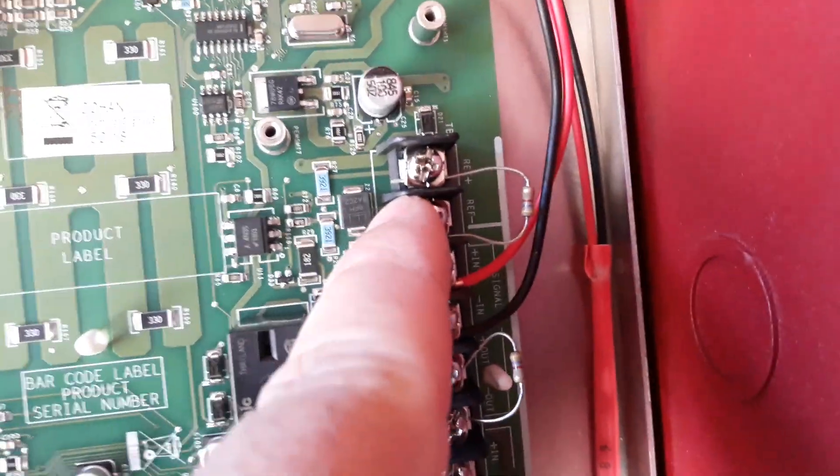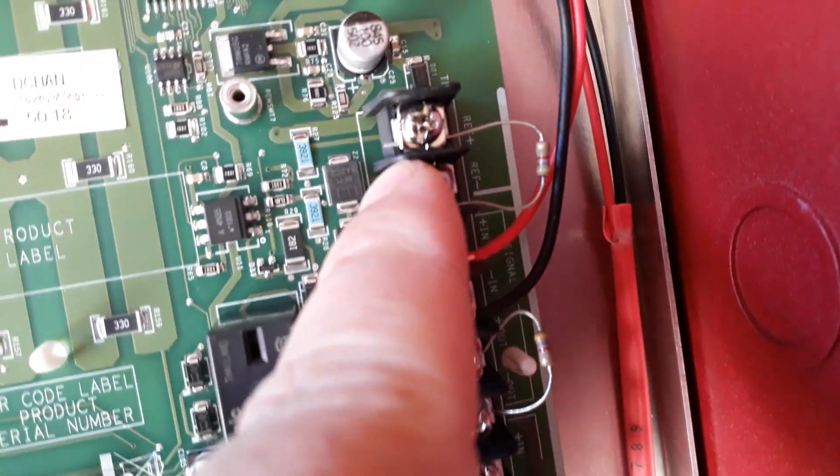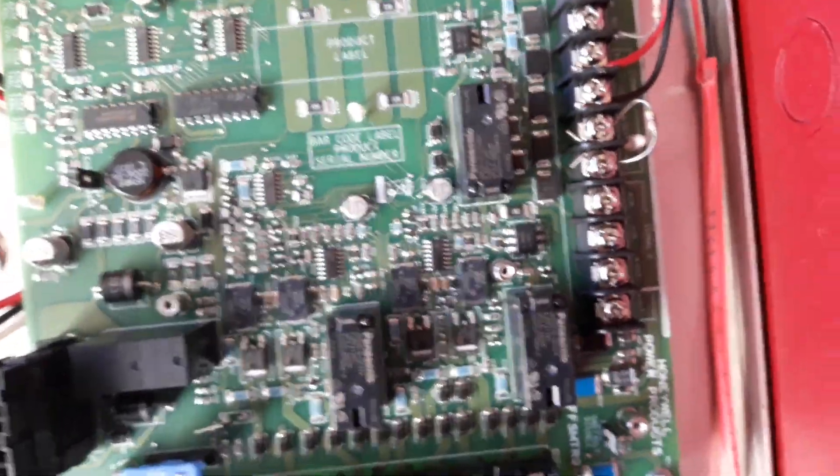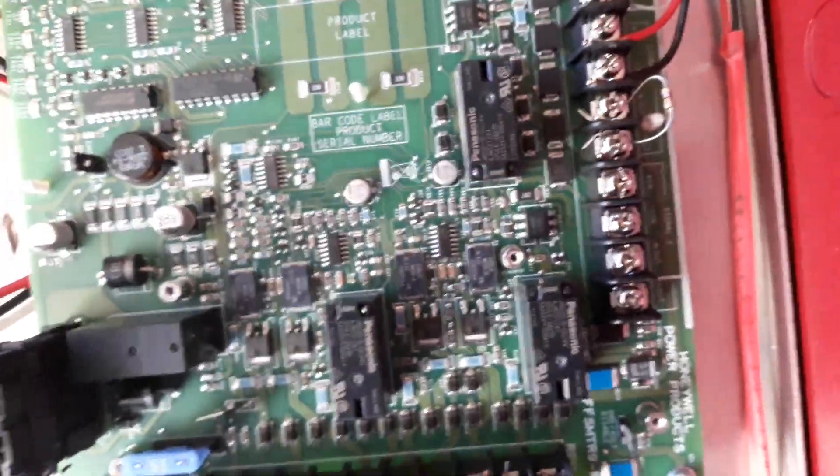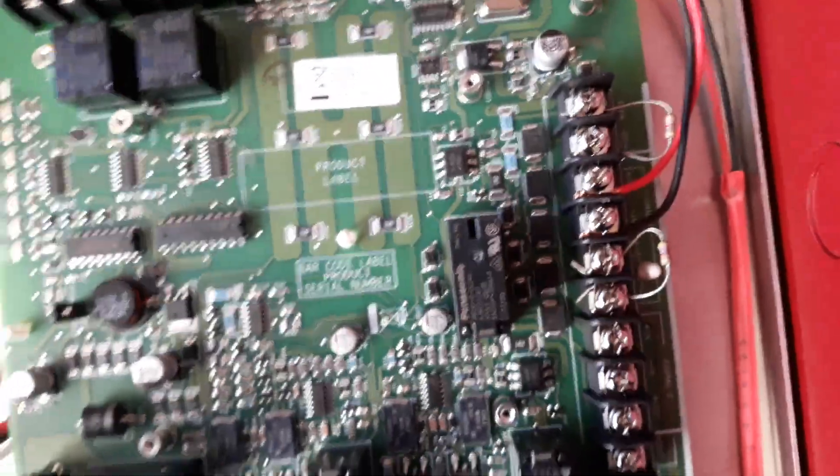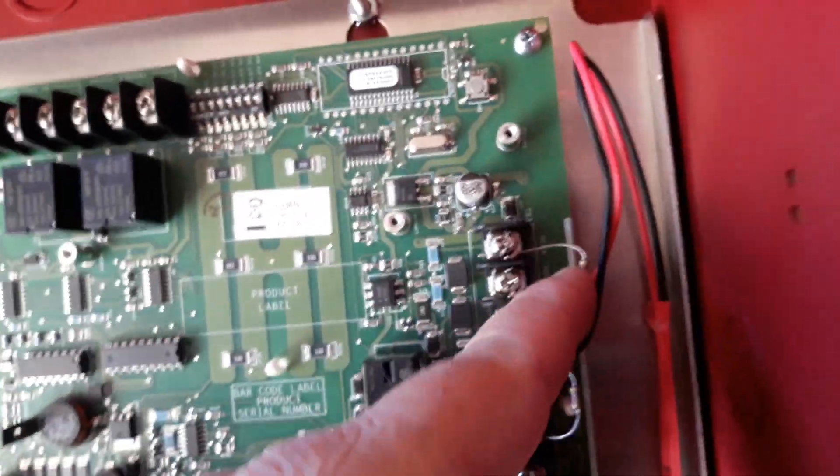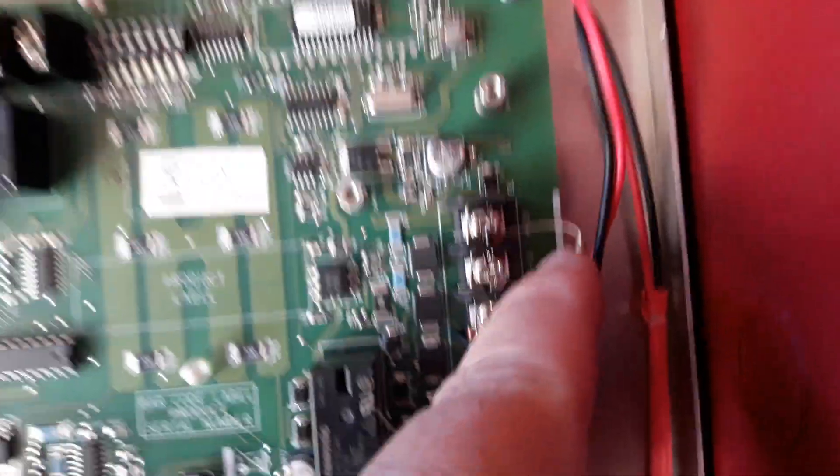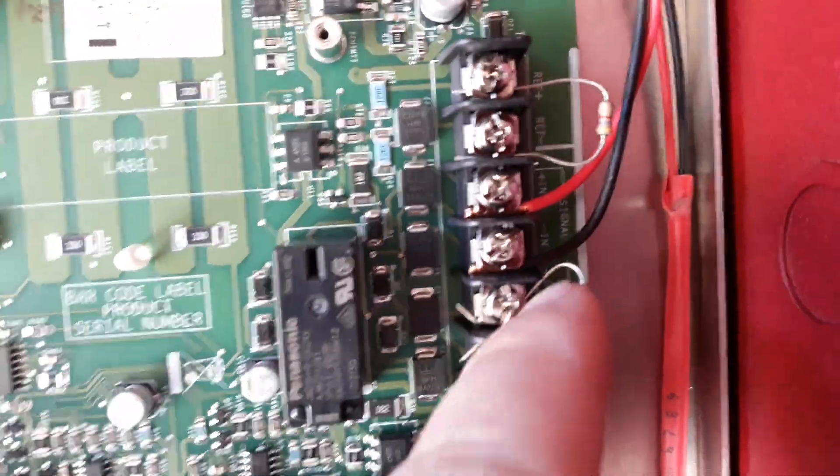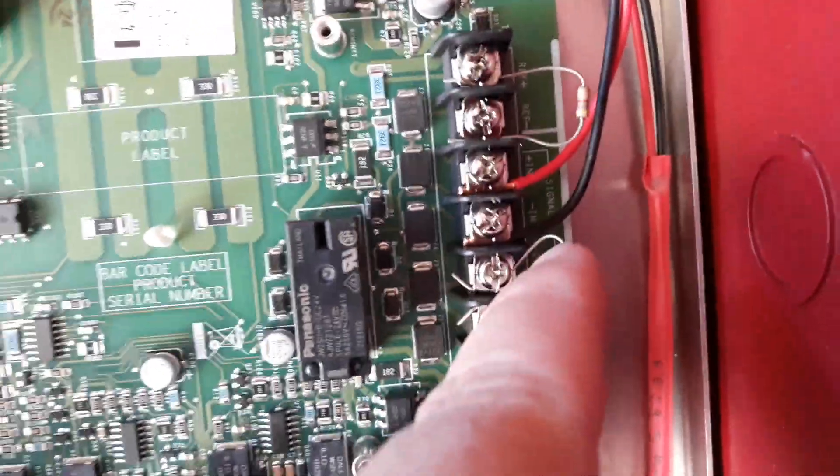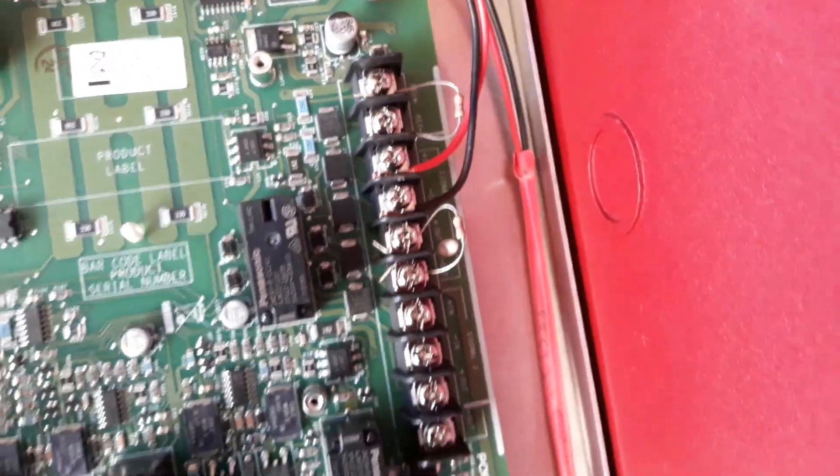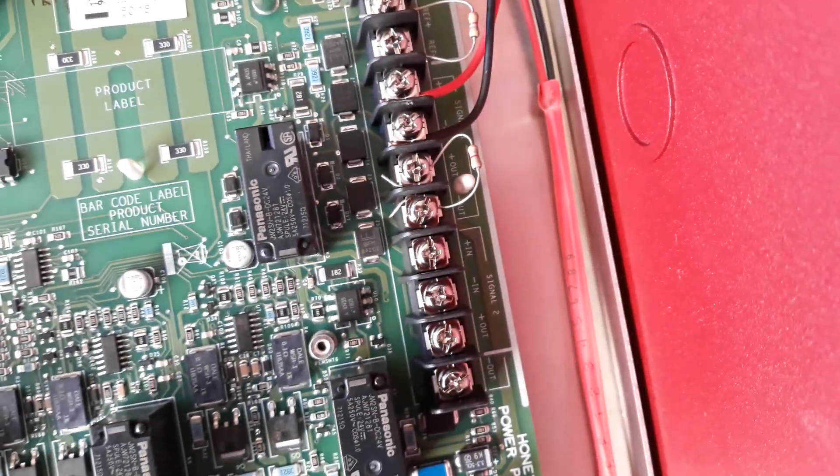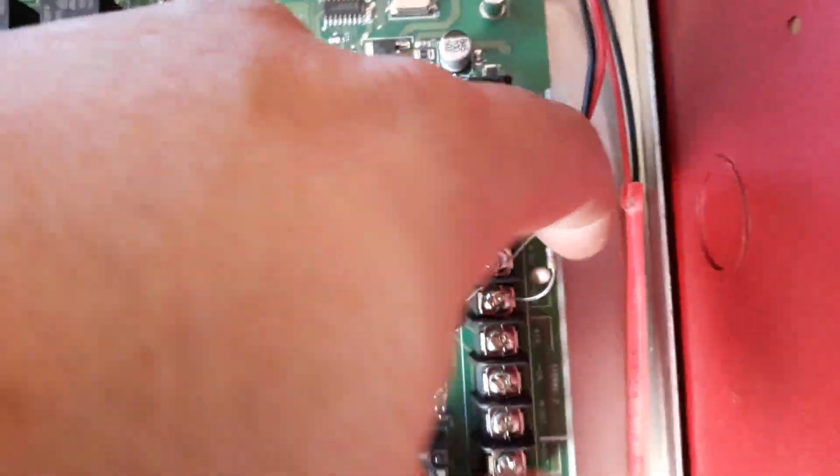Also, it has a reference resistor point. So let's say if you're going out there and you've got a Simplex wiring or whatever, or you've got System Sensor, or Gentex, or Wheelock, whatever. It'll have an end-line resistor. You just match up that end-line resistor right there. And you can change what end-line resistor it's looking for.